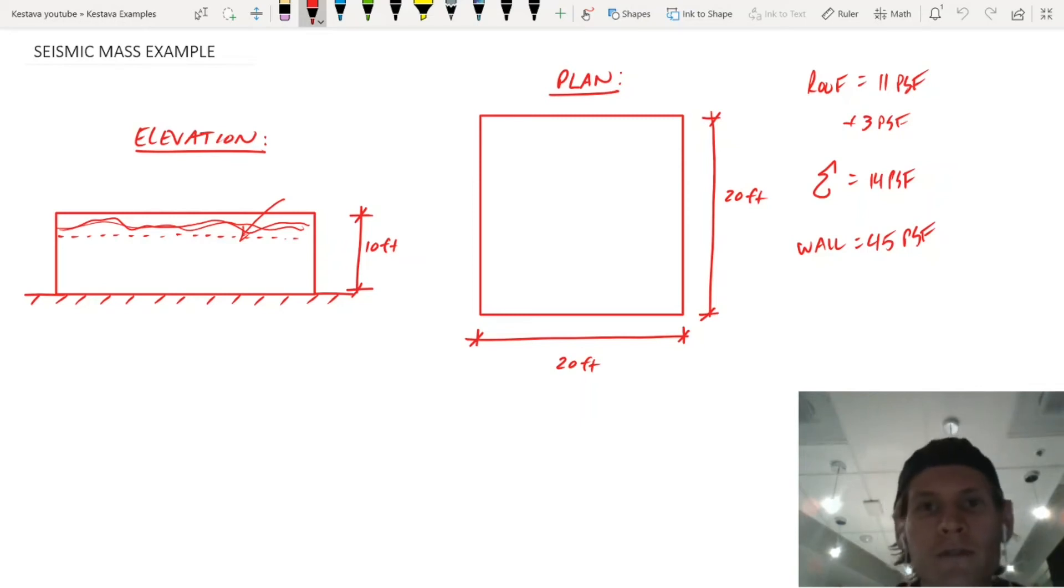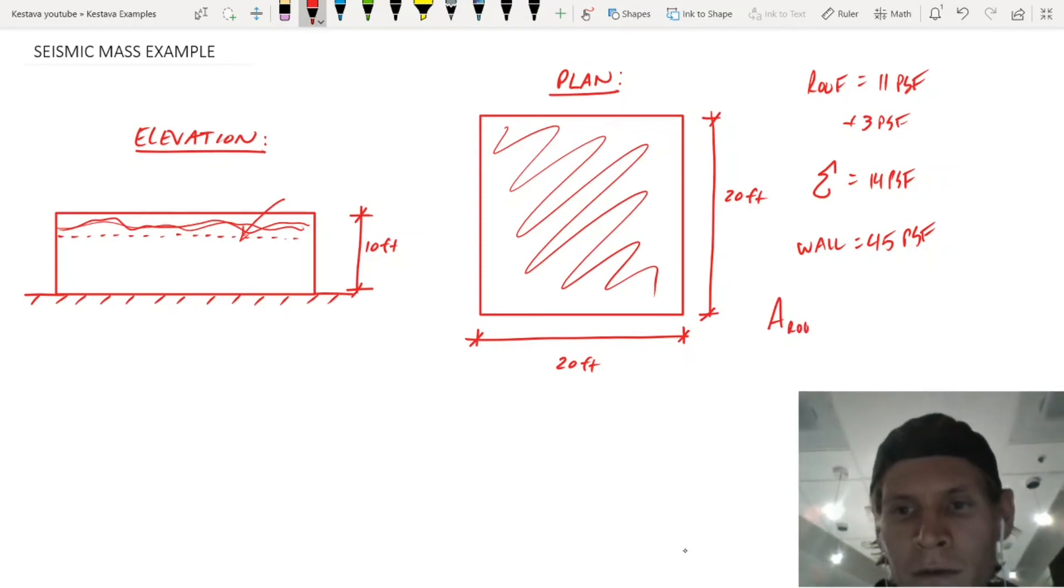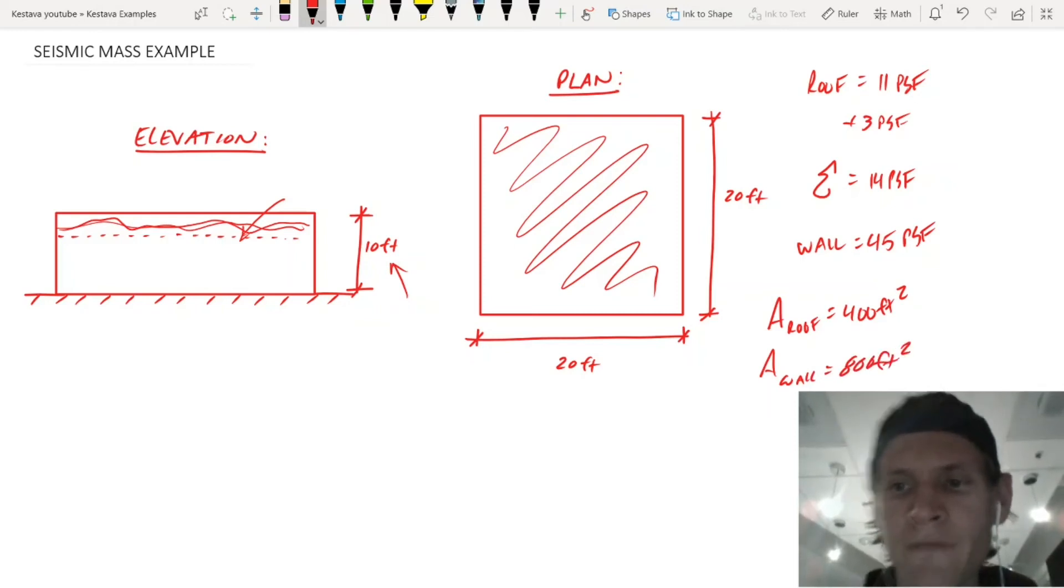All right, we have everything that we need. So all you do now is just multiply those pounds per square foot by some square footage. So roof, we'll do first. Roof, you're going to use the plan view, and we're going to get this entire area of the roof. So we have 20 by 20 is 400 square feet. Roof is 400 feet squared. And then for the perimeter of your wall, we know our wall is 10 feet. And we know that the perimeter is going to be four times 20 feet because there's four 20 foot long walls. 10 times 20 is going to be the square footage of one wall. That's 200 square feet. And we're going to multiply that by four to get 800 square feet. So area of wall equals 800 square feet.